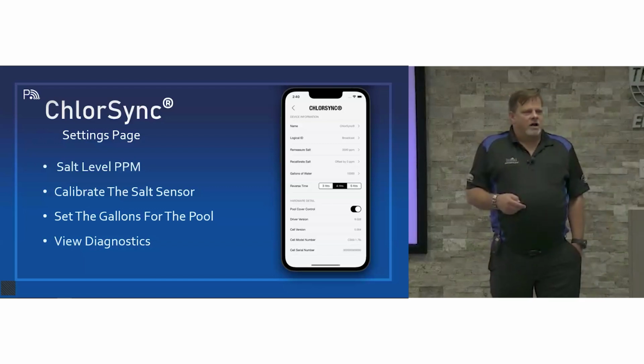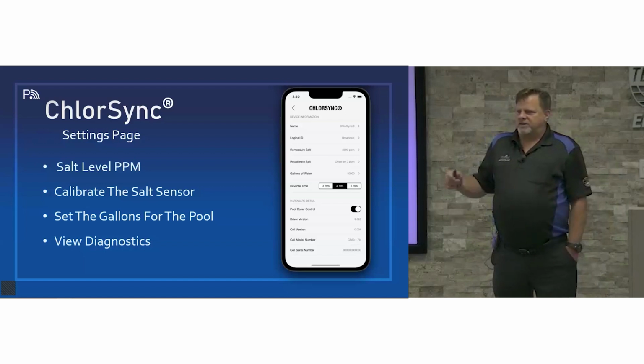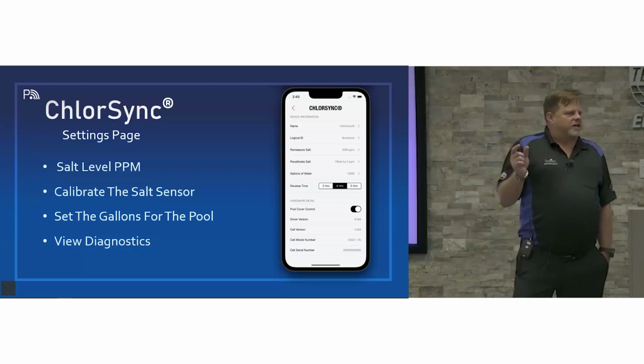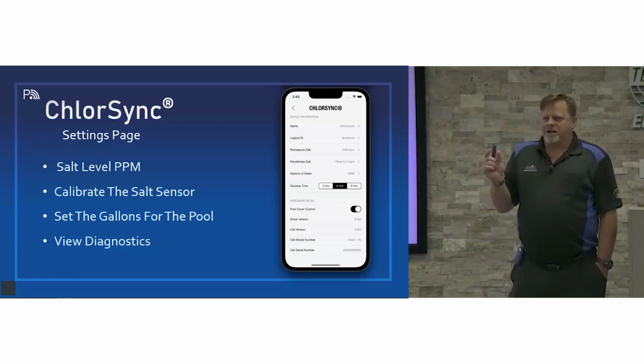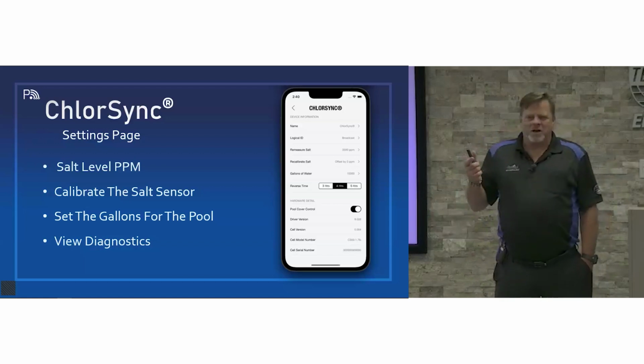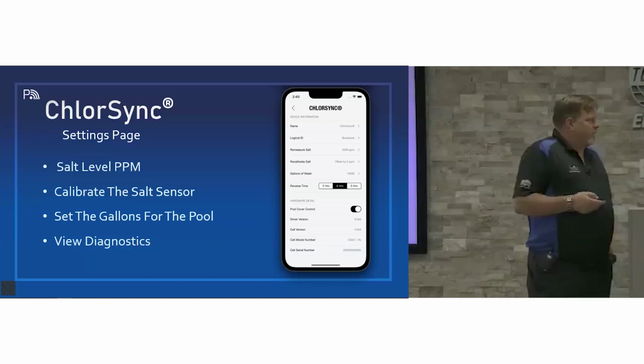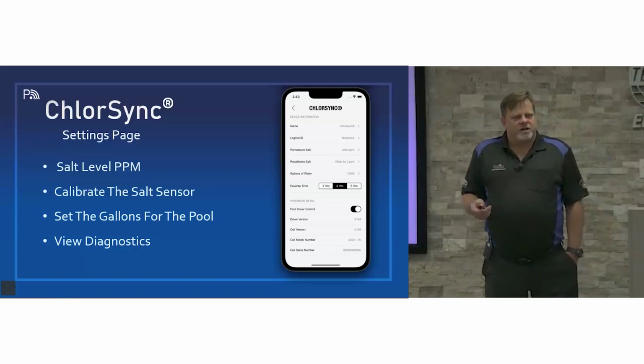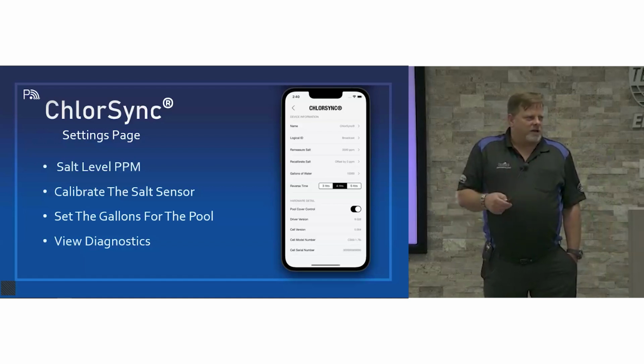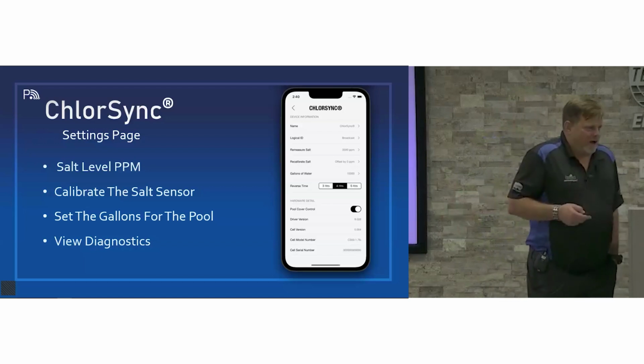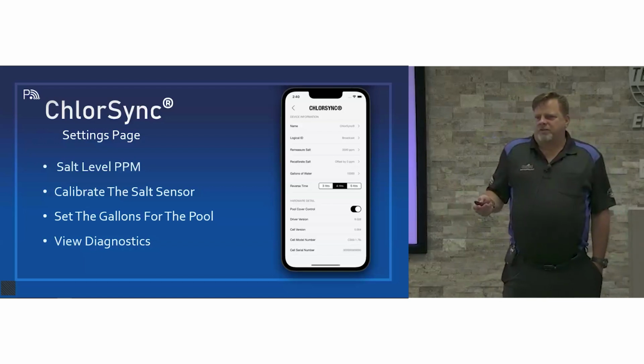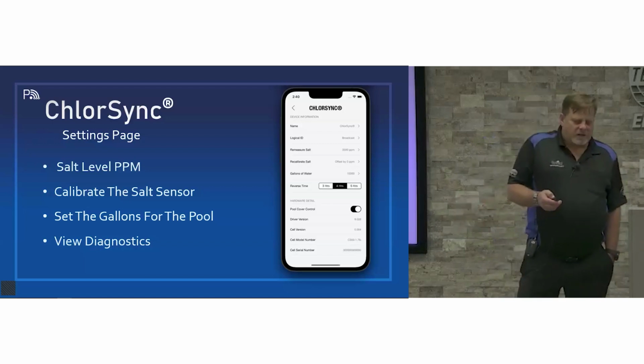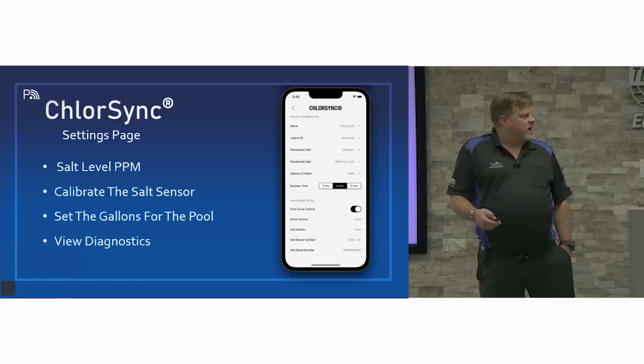So my simulator, however, because every unit is programmed to that simulator before it leaves the factory, is a resistor that doesn't change values, so long as you leave it in the Ziploc baggie and don't expose it to moisture to where it can corrode up or anything. But the resistance value on it does not change. So if I plug that in and it's supposed to read 7,000 and it's reading 7,000, then there's no reason for me to calibrate the unit. It's reading properly. The fact that it's reading different than your meter doesn't really mean a lot to me. Now, if it's 1,000, 1,500 off, then we need to be looking at something. Maybe the tri-sensors are scaled up. There's something going on. There's something offering more resistance than what's actually showing.